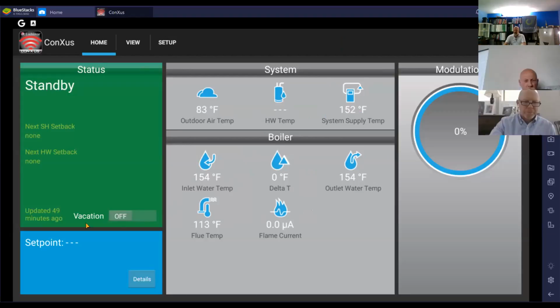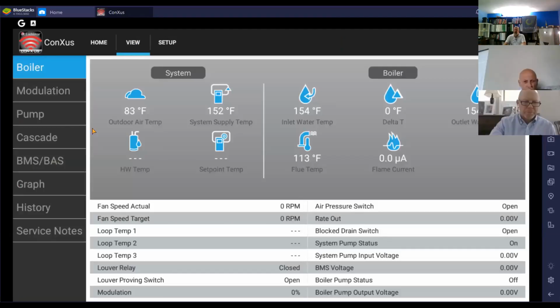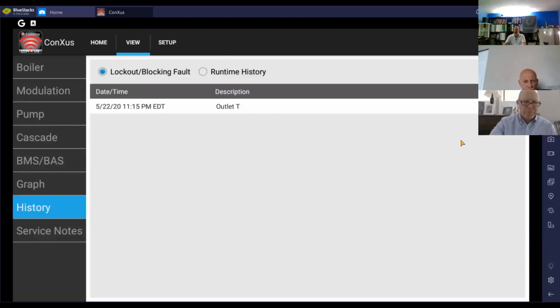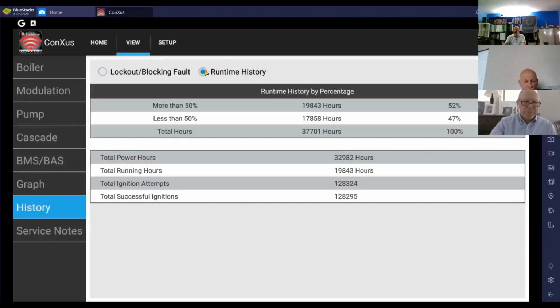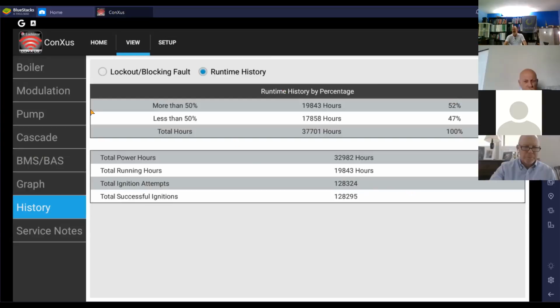Go take a look at, jump into the history and look at the runtime history. And that gives us an idea - this has really got a lot of ignition attempts right now. So 20,000 hours of run and 130,000 ignitions. It's not the end of the world, but it probably could get a little better. It's about 6.5 cycles an hour. I think we can certainly live with that.